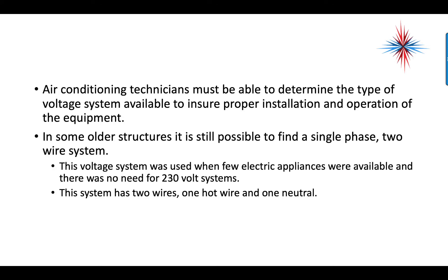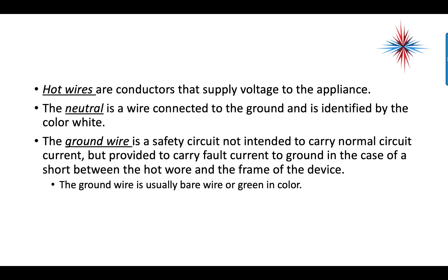Air conditioning technicians must be able to determine the voltage system available to ensure proper installation and operation of equipment. In some older structures, it is still possible to find single-phase two-wire systems. This voltage system was used when few electrical appliances were available and there was no need for 230-volt systems. The system has two wires: one hot wire and one neutral. Hot wires are conductors that supply voltage to the appliance. The neutral wire is connected to the ground, identified by a white color. The ground wire carries fault current to ground in case of a short between the hot wire and the frame of a device.